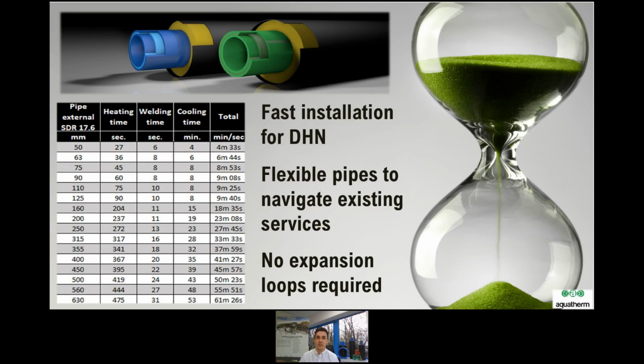Now, we all know that the advantages of district energy schemes are obvious. However, the right choice of piping material is of crucial importance. With Aquatherm's innovative TI range, TI meaning thermally insulated, you get a pre-insulated pipe system for underground installation, which is ideally suited to transport heating and cooling water safely and efficiently over long distances. The medium pipe, made of either Aquatherm blue pipe or Aquatherm green pipe, is insulated with PUR rigid foam and enclosed in a jacket made of polyethylene to protect it from damage by the surrounding soil.